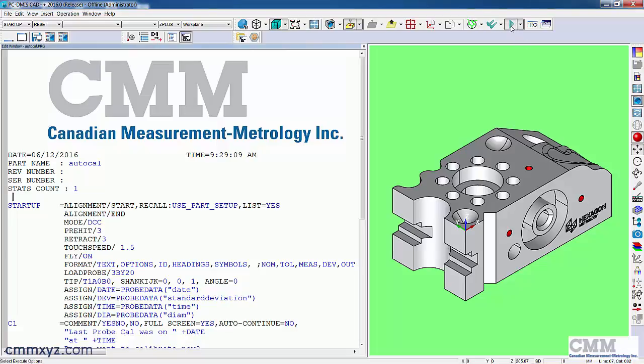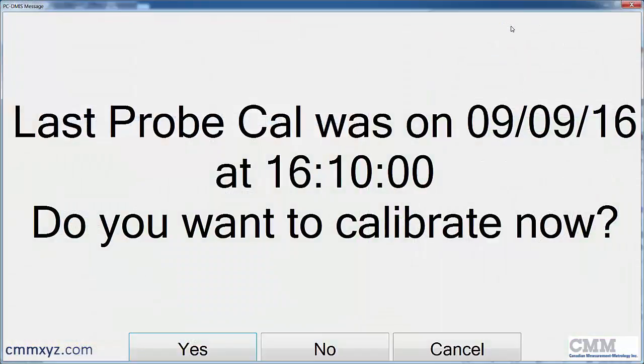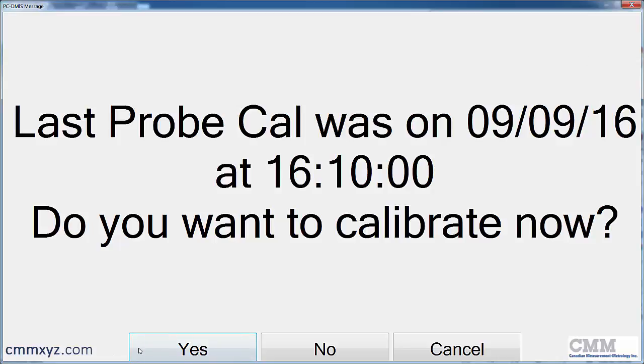We'll just hit execute. So you can see I've also used probe data to plug in the time of the last calibration. So I've also given the operator the option to calibrate now. So I'll say yes.